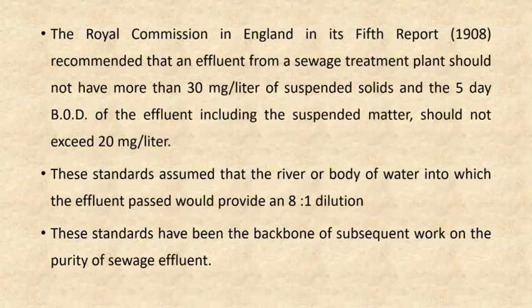So the Royal Commission in England in its 5th report recommended that effluent from a sewage treatment plant should not have more than 30 milligram per liter of suspended solids, and the 5-day BOD, the oxygen demand of effluent including the suspended matter, should not exceed 20 mg per liter.